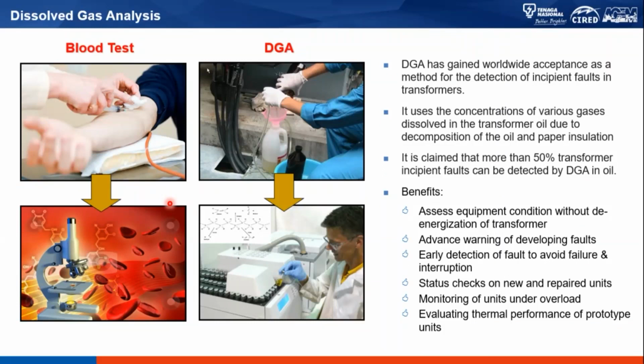And then we are going to look later how we talk about dissolved gas. So where do these gases come from? First of all, just understand that there are gases, and these gases are related to the faults, and somehow the concentration of these gases that is dissolved in the transformer oil can give us a lot of data, and that happens as a result of the decomposition of the insulating oil as well as the paper insulation. So right now, what we can understand is that these gases are the products of insulation decomposition, but we are going to look into that in detail later on.